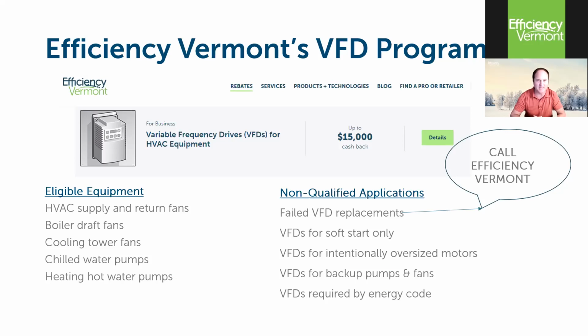Backup pumps and fans, this is a good one because some customers have redundancy in their system. We are not in the business of putting drives on redundant pumps and fans that run only as fail safes. The drive doesn't save any energy sitting there waiting for another pump or fan to fail. So we're not going to support those. And I've said it several times. Anything required by energy code is not going to be eligible for rebate. So next slide, please.